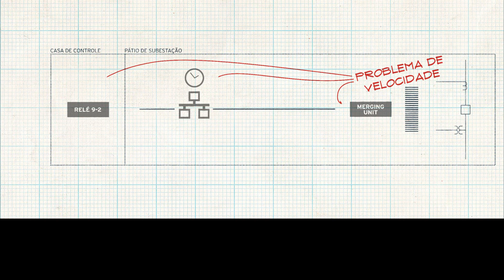Those are the challenges, and we worked with customers, and they said, hey, SEL, can you come up with a solution that's more point-to-point? Yep, we can do that. We took our existing 400 series relays and our Axion module that communicates over industry standard EtherCAT communications and created a solution that looks just like that. That's what we refer to as our time domain link, or TiDL technology, which is really cool. It addresses the problem with security. It's point-to-point. For reliability, there are only 2 devices instead of multiple, and the speed's pretty darn good.